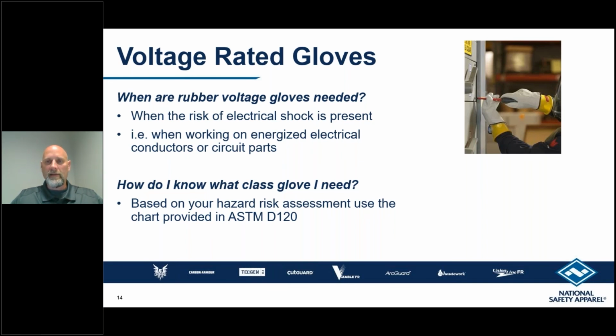You might ask, what's the difference? The difference is we invested in testing equipment. We do not retest gloves, but we do have testing equipment, so we can buy voltage rated gloves untested from the manufacturer, and they do not expire on our shelves. That way we can sit with inventory to support the marketplace when the need arises.